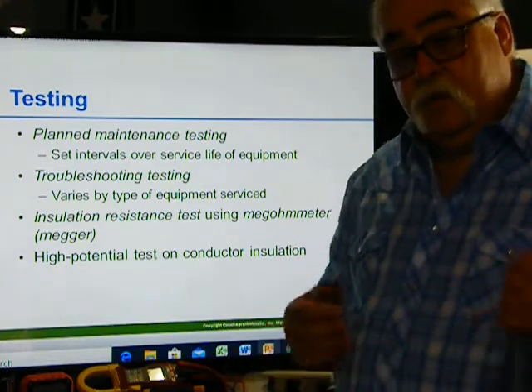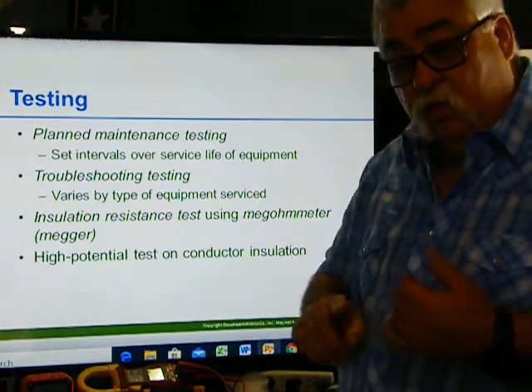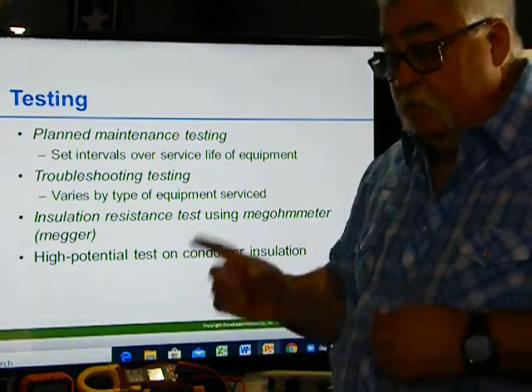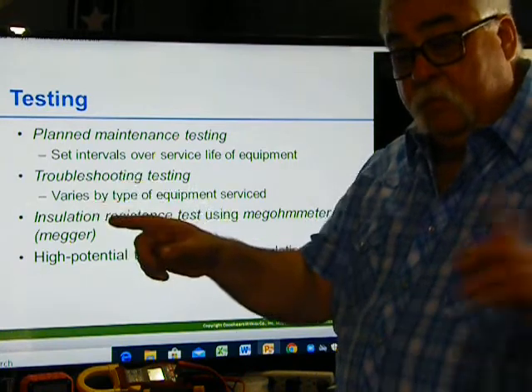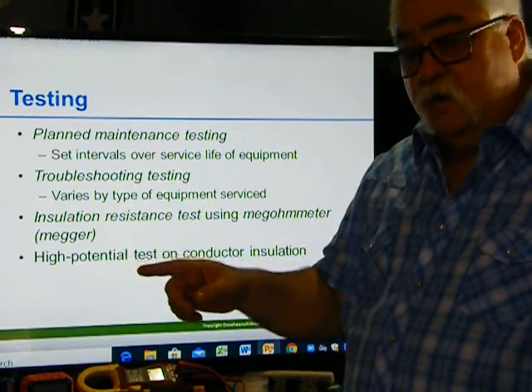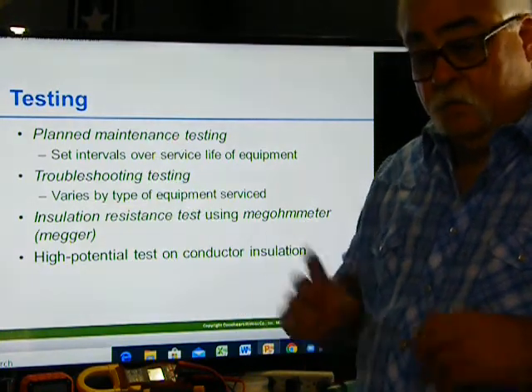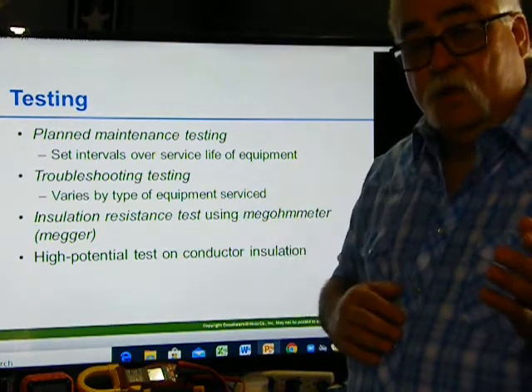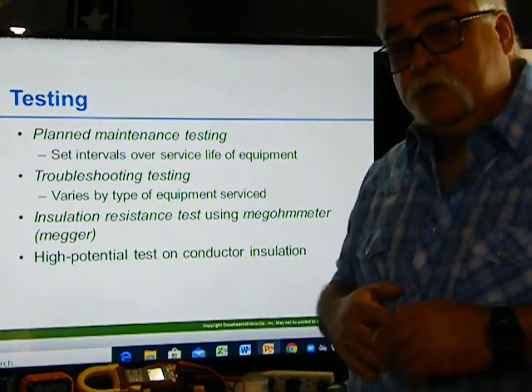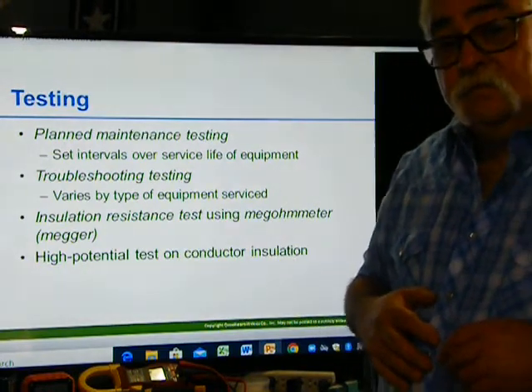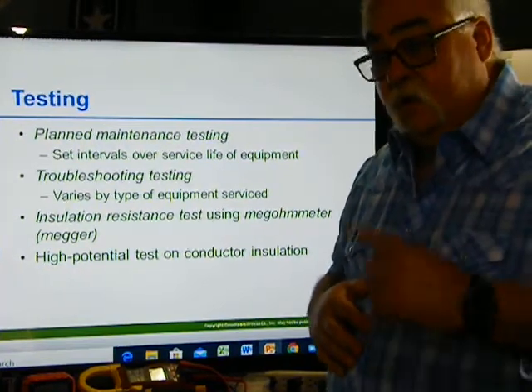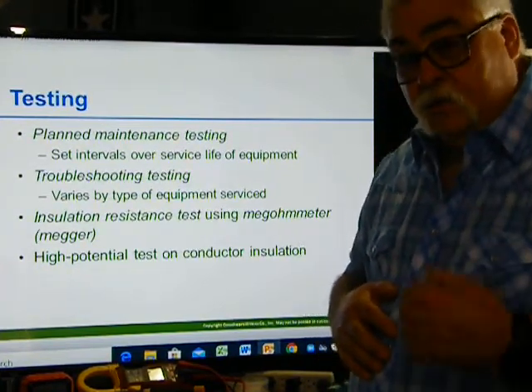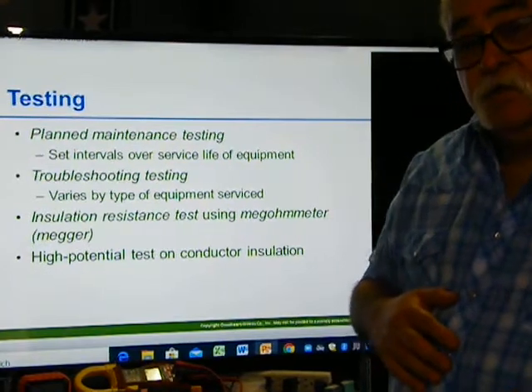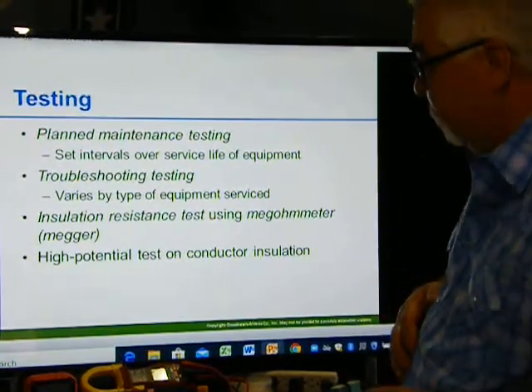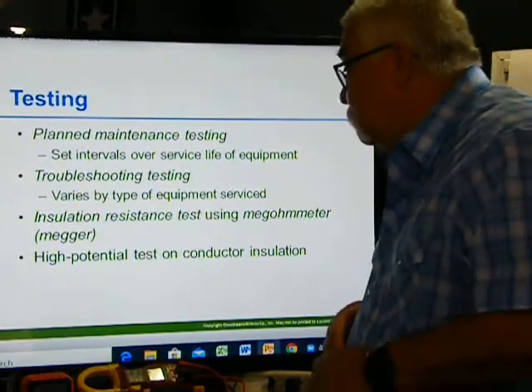Those are preventative things. The engineer walked in, he checked the oil levels, he checked everything. My preventative maintenance is not worrying about the generator. It's the transfer equipment. Make sure it's going to transfer when I need it. It's like, how many of you test your GFIs? How do you know your GFI is going to work if you don't test it once a month? The way the manufacturer specifies is preventative maintenance. That's what we used to go around doing in the hospitals.